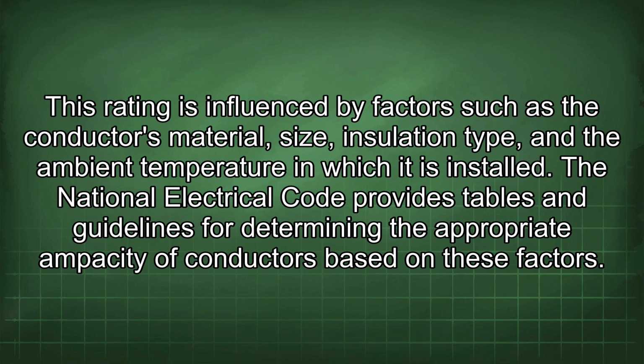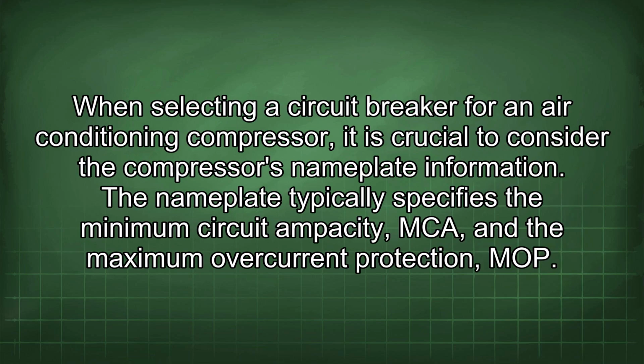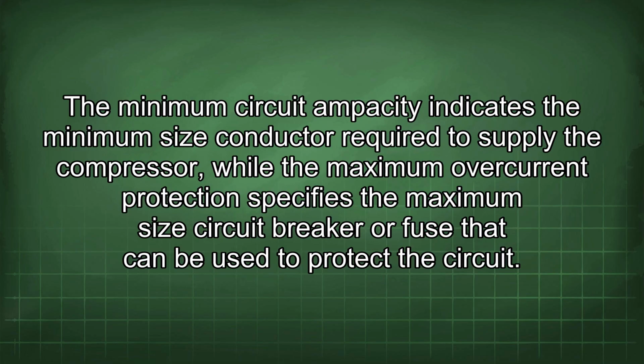When selecting a circuit breaker for an air conditioning compressor, it is crucial to consider the compressor's nameplate information. The nameplate typically specifies the minimum circuit ampacity, MCA, and the maximum overcurrent protection, MOP. The minimum circuit ampacity indicates the minimum size conductor required to supply the compressor, while the maximum overcurrent protection specifies the maximum size circuit breaker or fuse that can be used to protect the circuit.